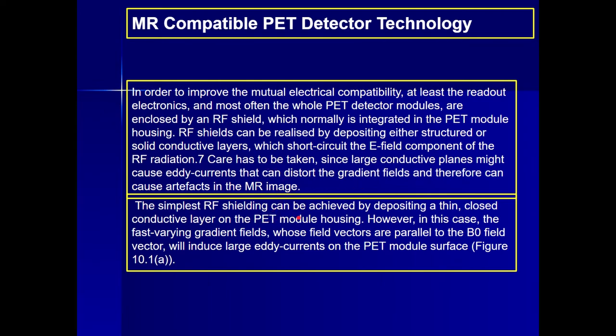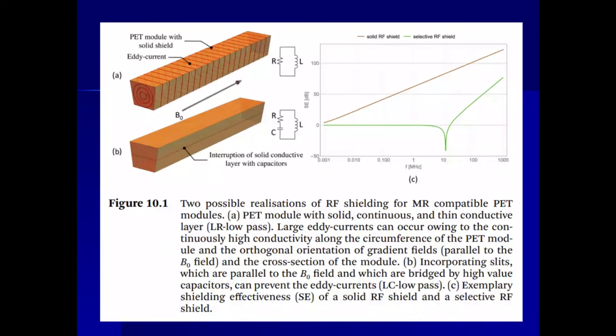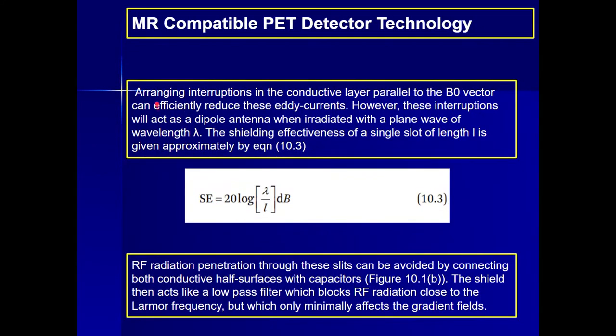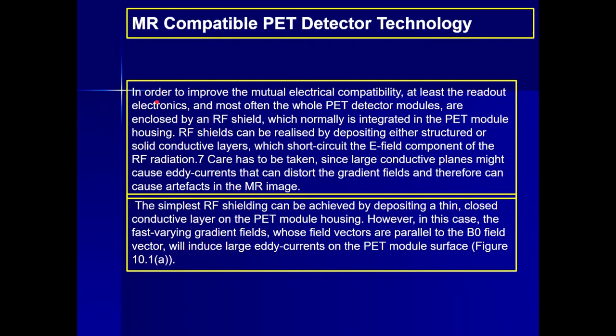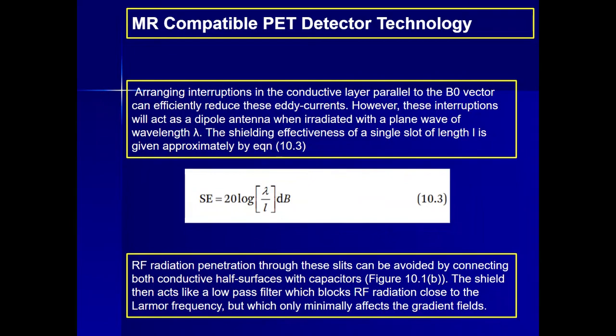The simplest RF shielding can be achieved by depositing a thin closed conductive layer on the PET module housing. However, in this case, fast varying gradient fields whose field vectors are parallel to the B0 field vectors will induce large eddy currents on the PET module surface. Figure 10.1. Arranging interruptions in the conductive layers parallel to the B0 vector can efficiently reduce these eddy currents.